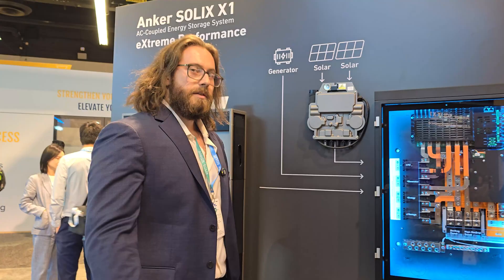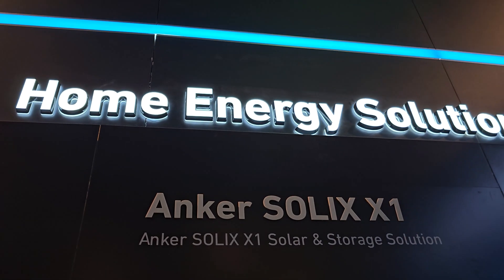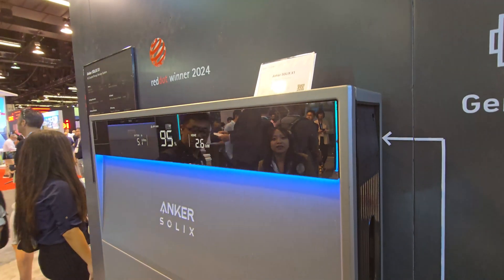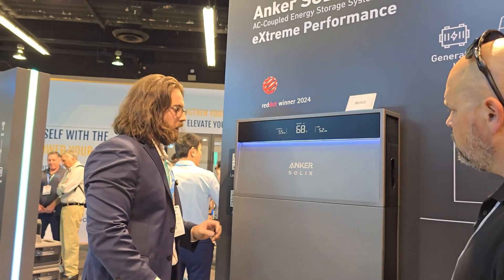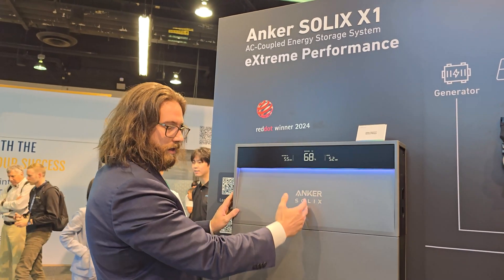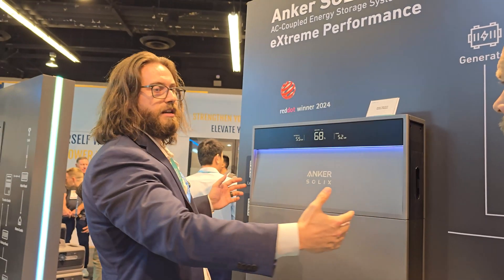My name is Michael. I'm a solutions manager at Anker. I'm going to talk to you about our home residential storage energy solution. This is our Anker SOLIX X1. We've got batteries here on the bottom — each one of these is five kilowatt hours. The inverter is right here on the top. It's got the display. The output of this top inverter is six kilowatts, and everything here is parallel, so you can have multiple stacks next to each other and expand the system.